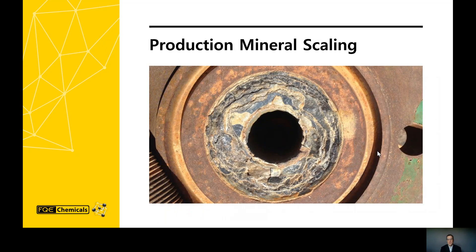During production, mineral scale is formed. The main types found in oil and gas facilities are sulfate scale, such as barium sulfate and strontium sulfate, and calcium carbonate. As shown in previous slides, radium has a similar radius to barium, strontium, and calcium, and hence co-precipitates to form radium sulfate, radium carbonate, and in some cases, radium silicate. The mineral scale shown here in the image would be analogous to the mineral scale you may see at your home from a hard water source.